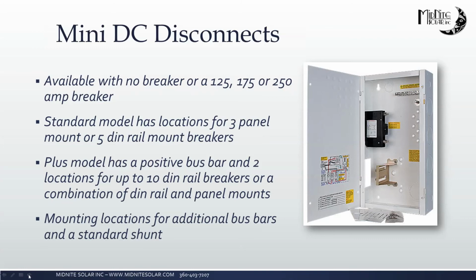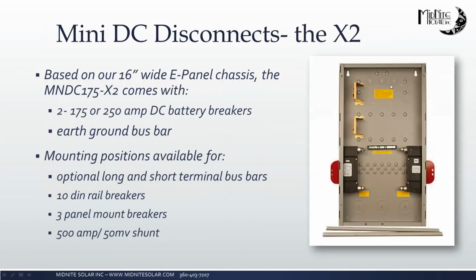And it has mounting locations for the additional bus bars as well as for a standard shunt. So if you want to use it with our Whiz Bang or anything else that is with that shunt, it does have a location for mounting that. The Mini DC Disconnect X2 gives you 2 of the breakers in the 175 or 250 amp versions, an earth ground bus bar, and it has mounting positions for long and short bus bars, 10 DIN rail breakers, 3 panel mount breakers, and it also has the mounting location for, again, that shunt that you can use for current sense monitoring.